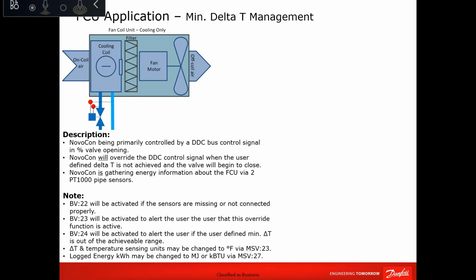So you would know exactly, if you are using the Novocon, let's say in a shopping mall, which we did already, and it starts controlling delta T, which shop is having issues and bringing a low return temperature to your system. You can tell him that either he's using the wrong solution or he's having a problem with maintenance, maybe his air filter, maybe his coil, something is wrong in his area that needs to be rectified. That's why the Novocon is disregarding the local control and enabling the minimum delta T management.